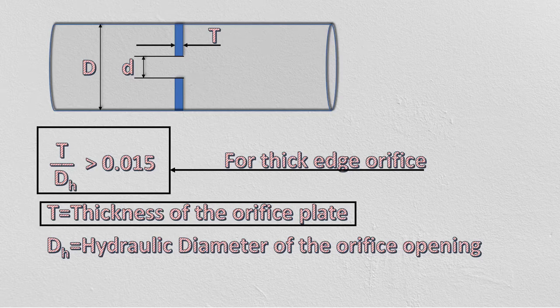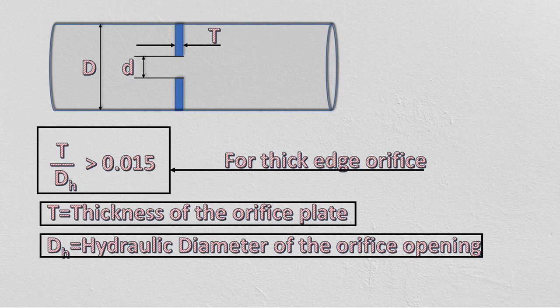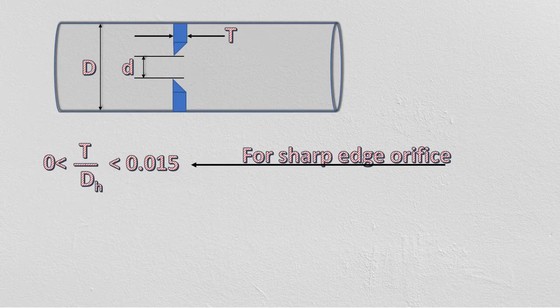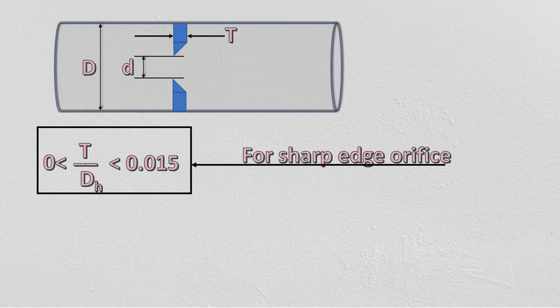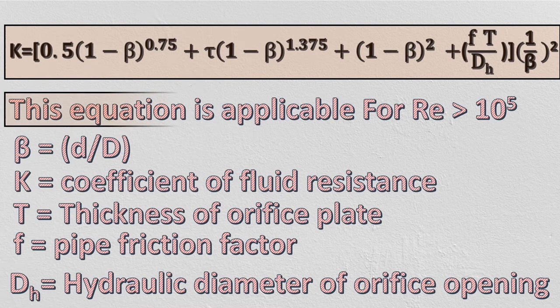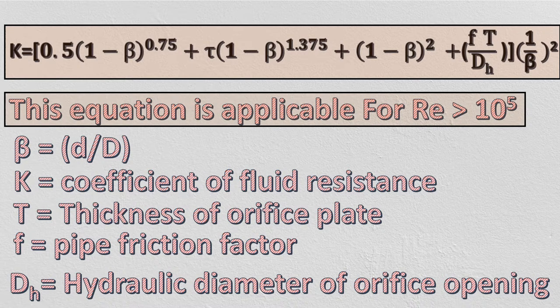Thick edge means the ratio of orifice plate to the hydraulic diameter of orifice opening shall be greater than 0.015. For sharp edge, this ratio lies between 0 to 0.015. This equation is applicable for Reynolds number greater than 10 to the power 5.